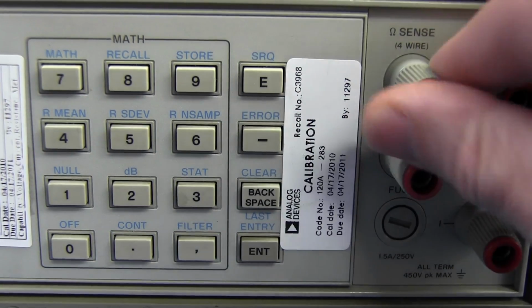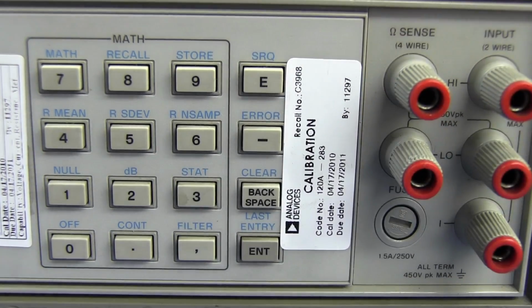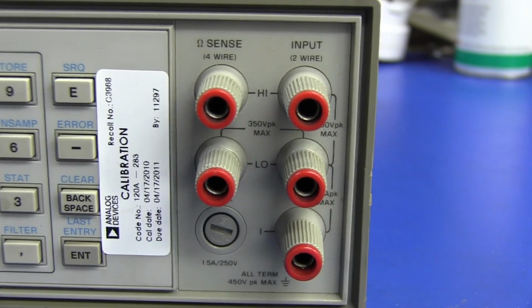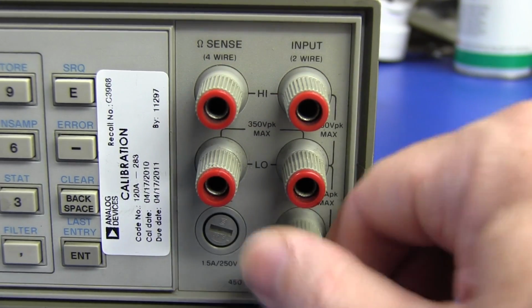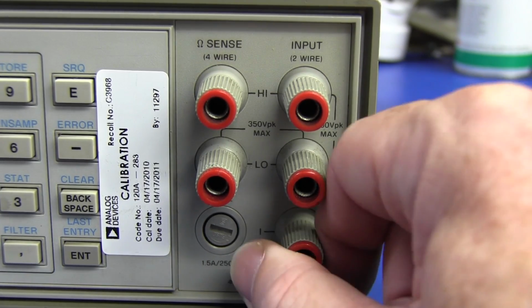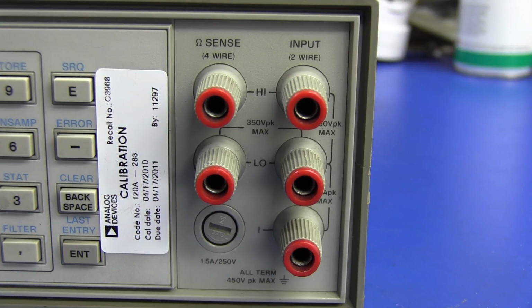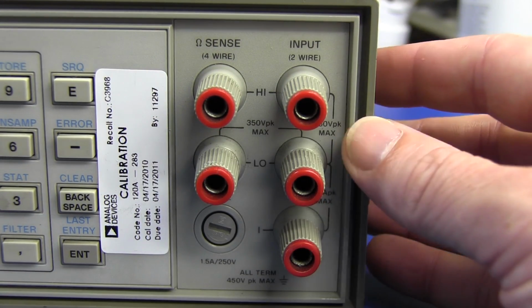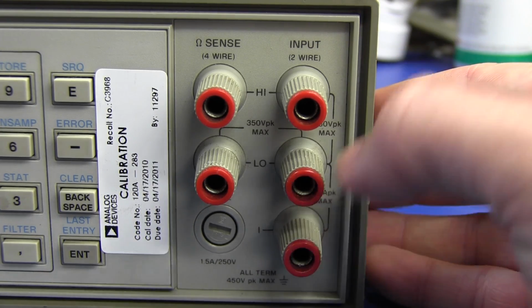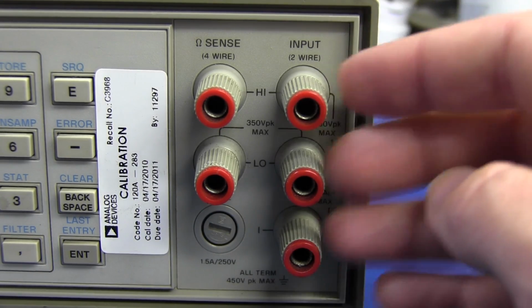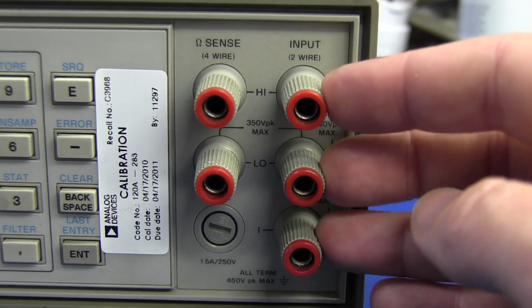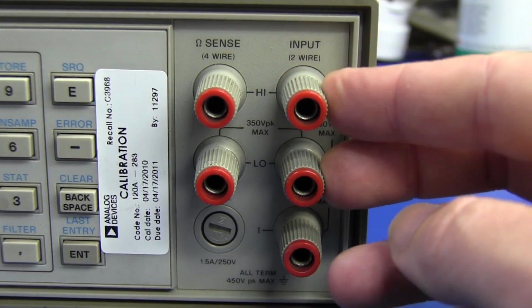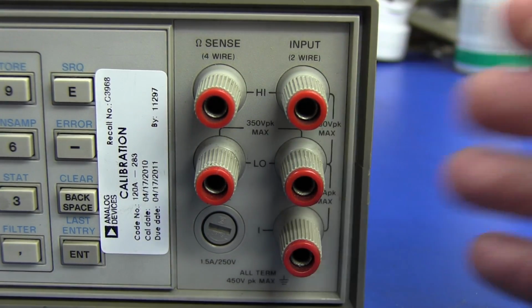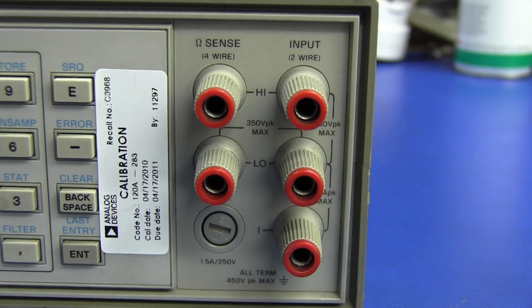And of course, we've got proper binding post inputs here. It's got 4-wire input for ohms, and separate current, fused current terminal down here. Now, there's one minor disadvantage compared to the 3458A this one's replacing in my lab here. It's only got the front panel terminals. It doesn't have them duplicated on the back. For my purposes, it doesn't matter a rat's ass, but if you're wiring these into a production test rack or something like that, that sort of thing could matter.